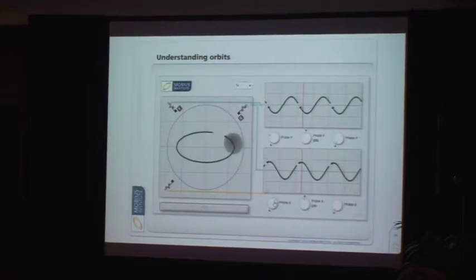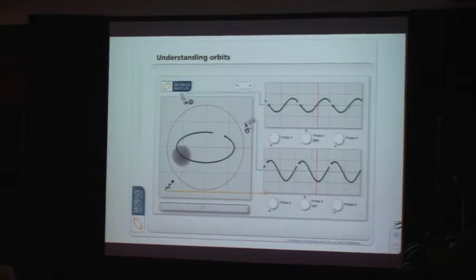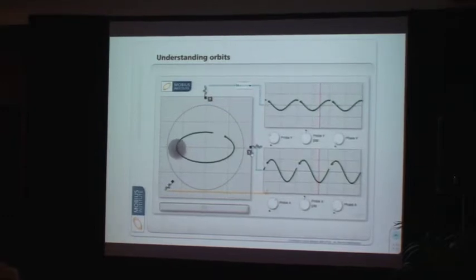And this is one of the tricky things too. If you look at this, you see that the two signals have a certain amplitude, and in fact the amplitudes of both of them are somewhat similar the way I've got it right now. But if the probes had been mounted here, you might notice that now the Y signal is much lower in amplitude and the X signal is now much higher in amplitude. So this is something you have to keep in mind when you set alarm limits and all of that.